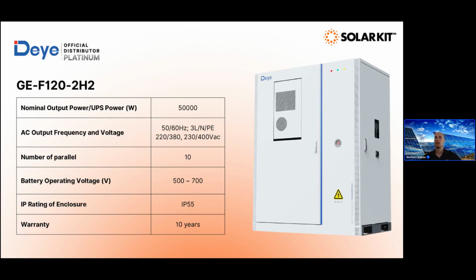But here you can see you have 50 kilowatt nominal output power and also the UPS power, because the inverter has a UPS port. So you can directly connect the PV cables to this inverter, and then you can connect the grid and the EPS loads separately. It can also work in off-grid mode. Also, you can connect 10 of these in parallel. Also IP55 and 10 years warranty, which is really a lot to consider, because 10 years is a lot for this kind of big C&I solutions.